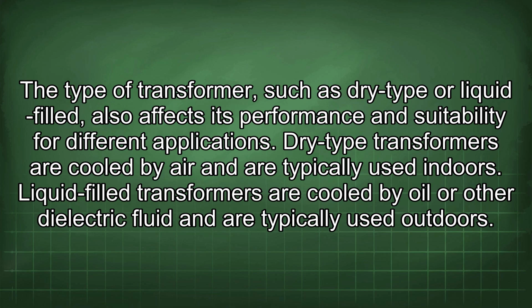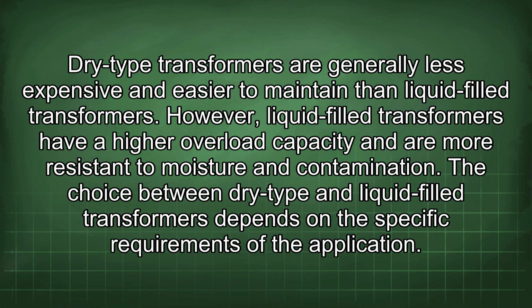Dry type transformers are cooled by air and are typically used indoors. Liquid filled transformers are cooled by oil or other dielectric fluid and are typically used outdoors. Dry type transformers are generally less expensive and easier to maintain than liquid filled transformers. However, liquid-filled transformers have a higher overload capacity and are more resistant to moisture and contamination. The choice between dry-type and liquid-filled transformers depends on the specific requirements of the application.